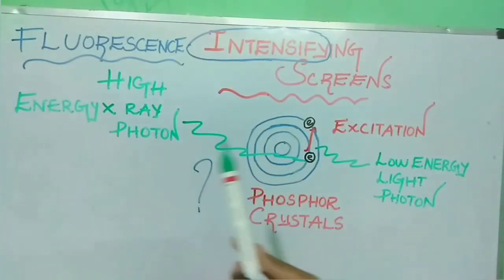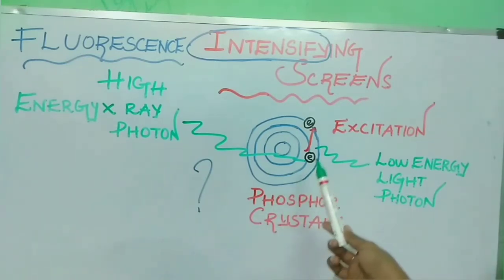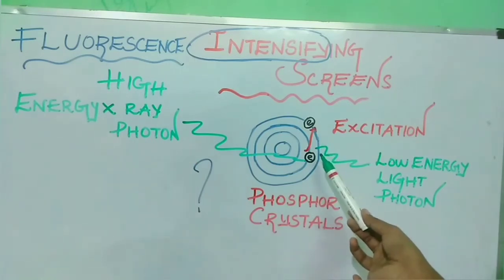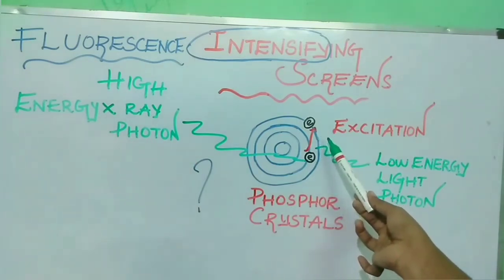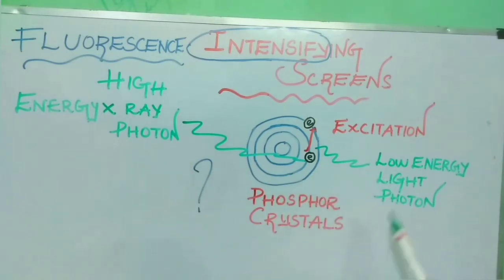How are high energy x-ray photons getting converted to low energy light photons? The main principle behind this conversion is fluorescence. When high energy x-ray photons interact with phosphor atoms there will be excitation. Excitation is the movement of an inner shell electron towards the outer shell. When this electron returns back to its original ground state there will be emission of low energy light photons. That is known as fluorescence.